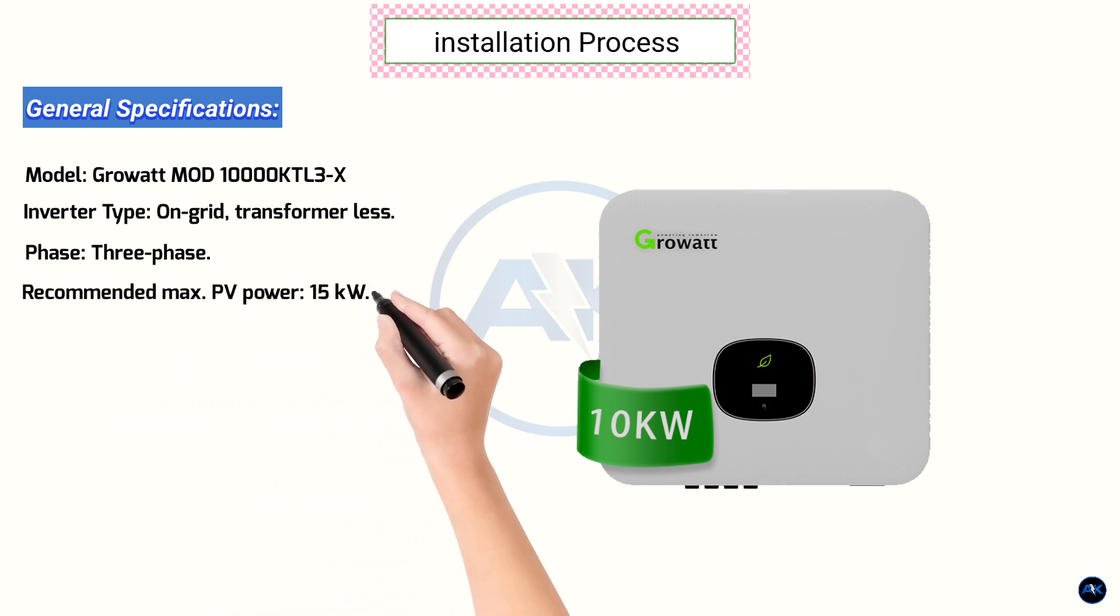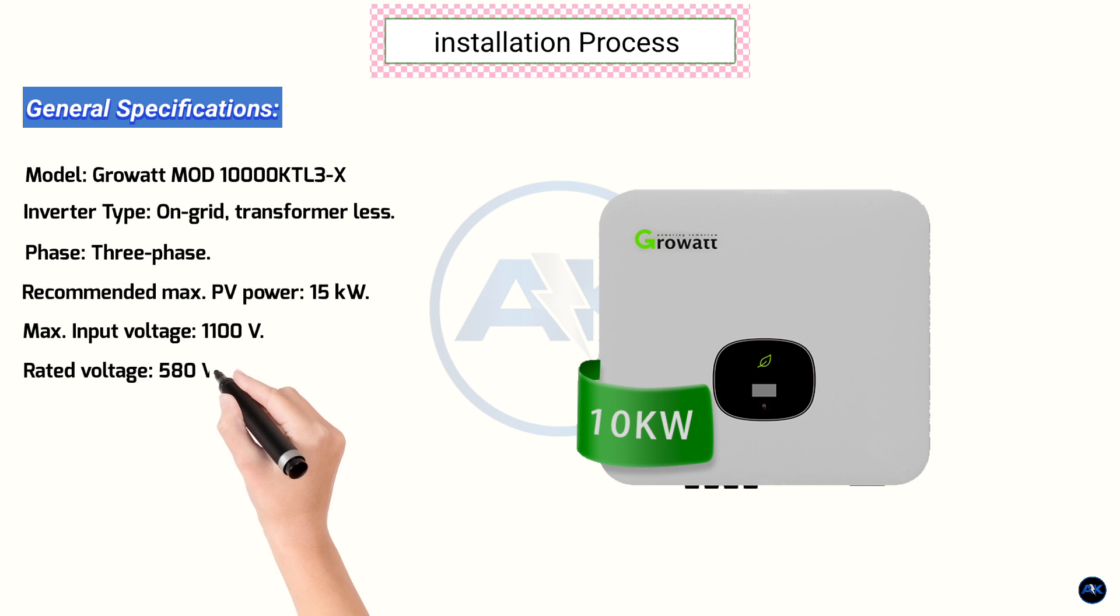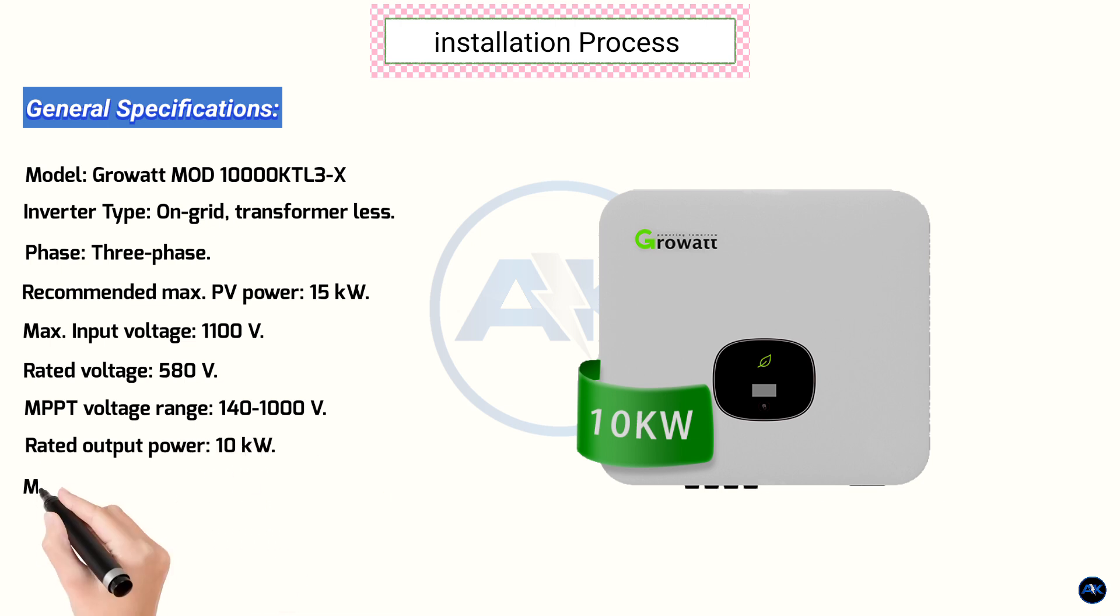Recommended max PV power 15kW, max input voltage 1100V rated voltage 580V, MPPT voltage range 140 to 1000V, rated output power 10kW, max output power 11kW, max efficiency 98.6%, operating temperature range -25 degrees C to plus 60 degrees C.